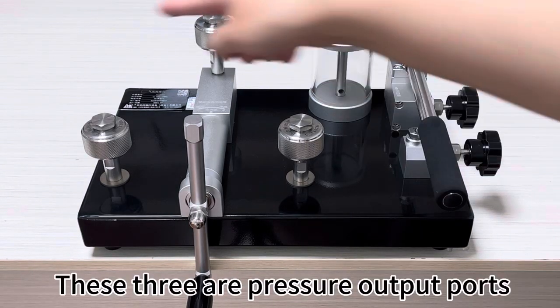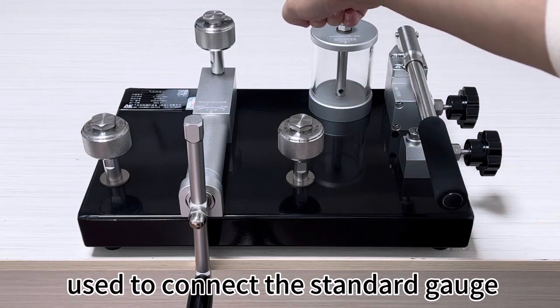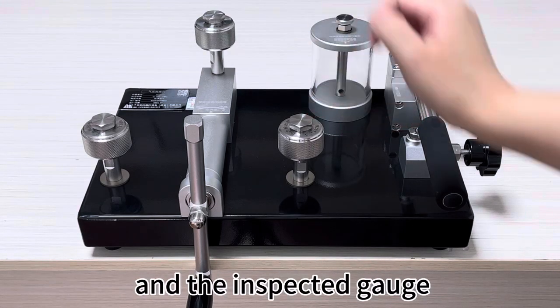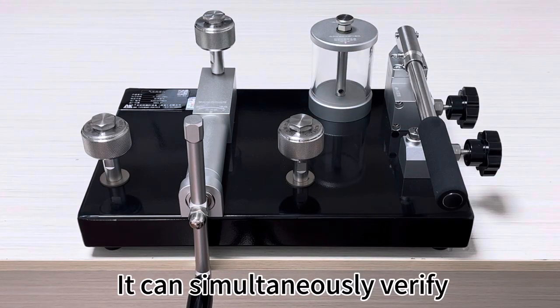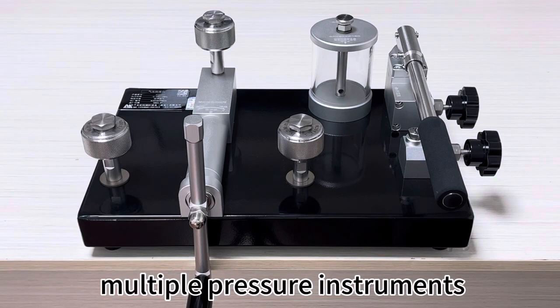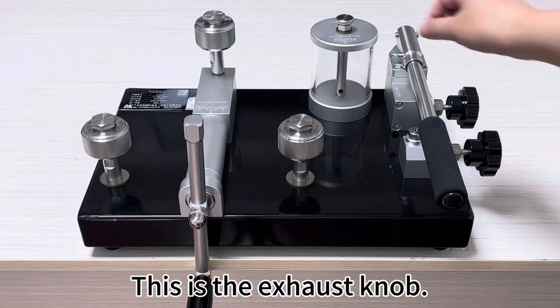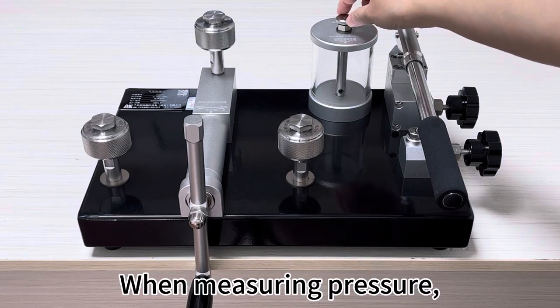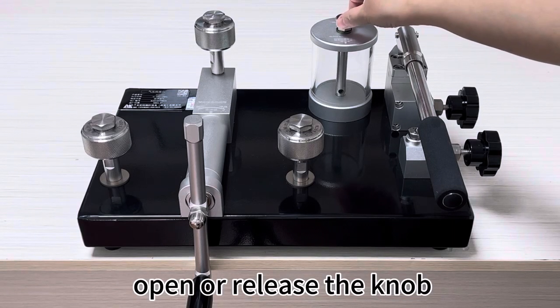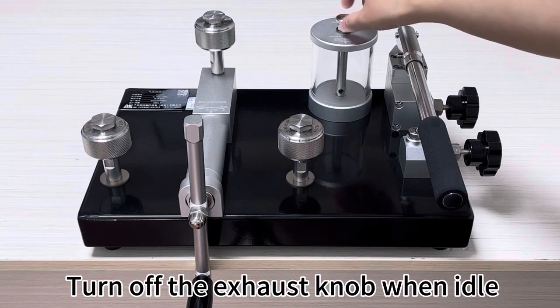These three are pressure output ports used to connect the standard gauge and the inspected gauge. It can simultaneously verify multiple pressure instruments. This is the exhaust knob. When measuring pressure, open or release the knob. Turn off the exhaust knob when idle.